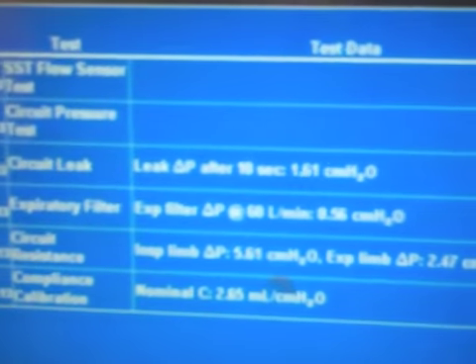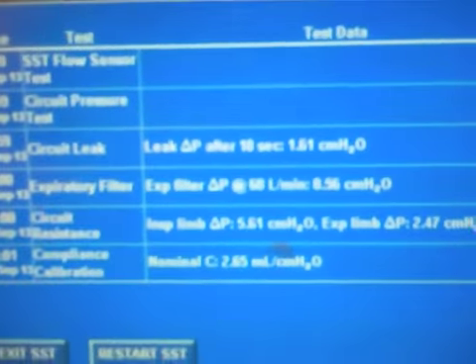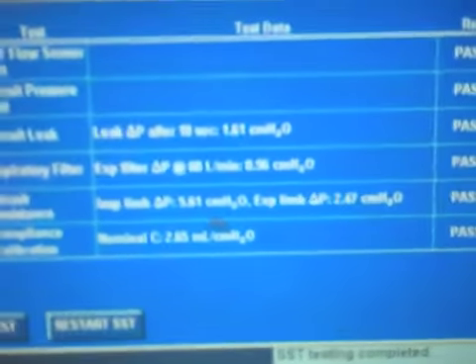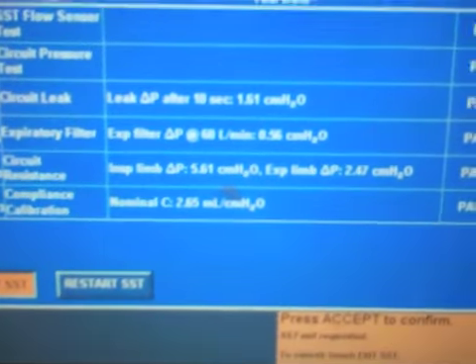Unblock the Y, and my SST is complete. You can see I've passed all my categories. Those numbers that are calculated for leak, expiratory filter, resistance, and compliance will now be saved. And to exit out, you just go to Exit SST, hit Accept, and you can start to set up your ventilator.